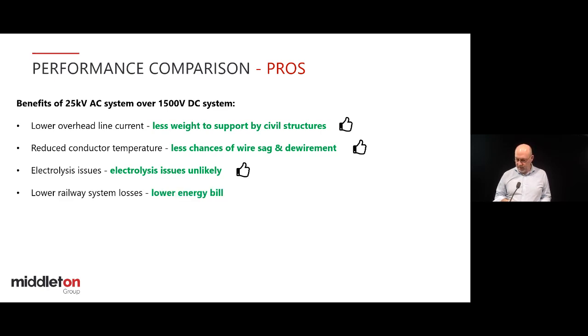Because of the much lower currents, there's a lot less losses. Also, there are fewer transformation points, so there are fewer feeder stations than there are substations in the DC system, which is the next point. But it also contributes to the lower energy bill from an AC 25 kV system. Just for example, some work we did recently looked at the rail system in Melbourne, the new system from Sunbury to Pakenham, where the two lines will be joined through the new tunnel. It's about 100 kilometres.